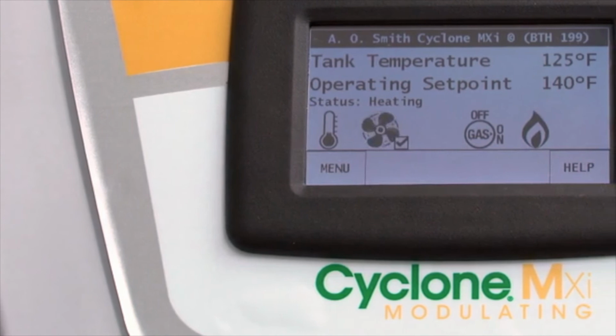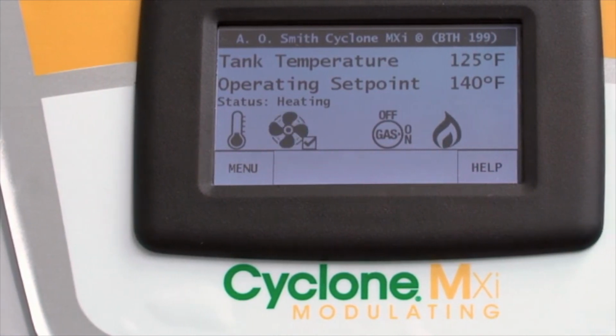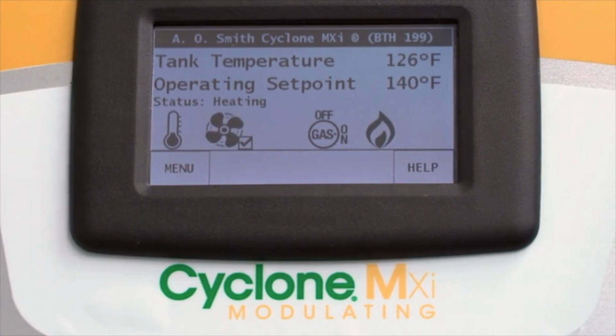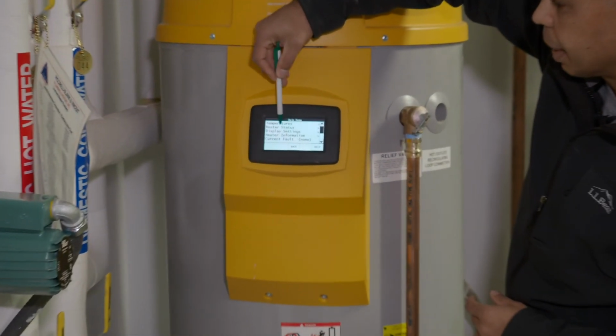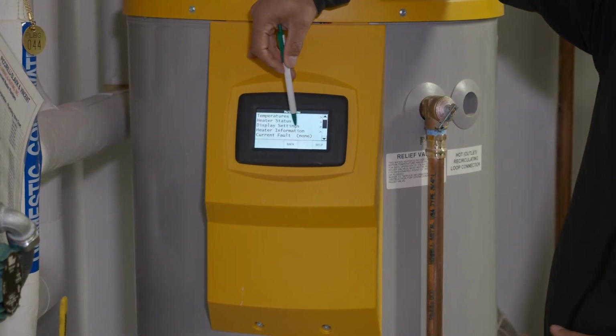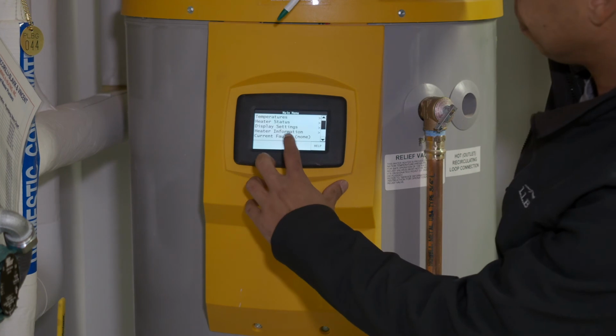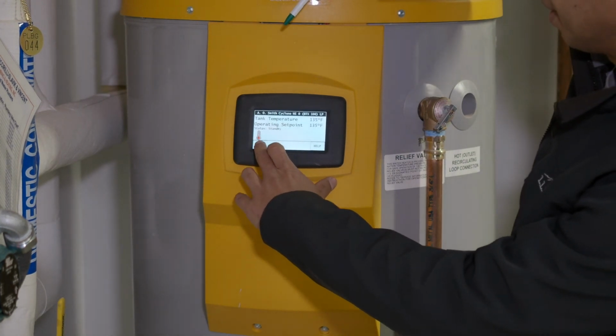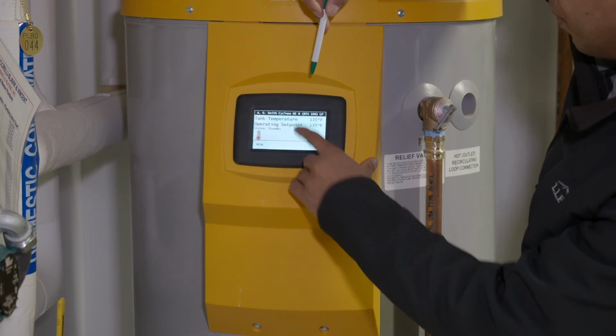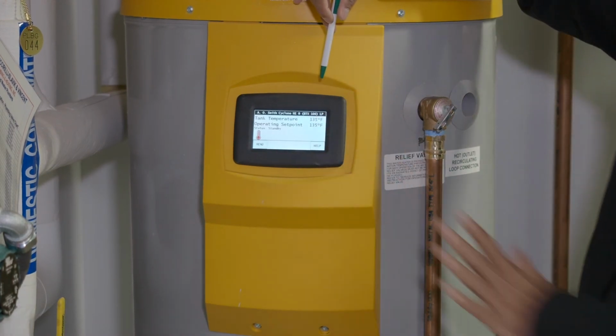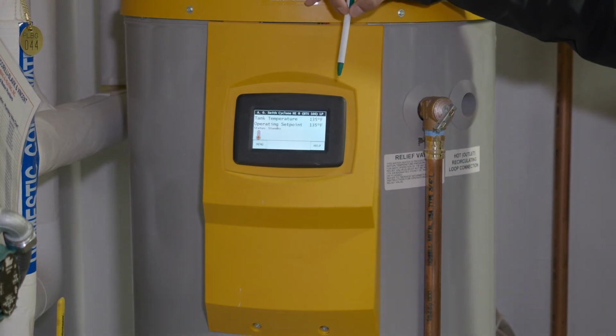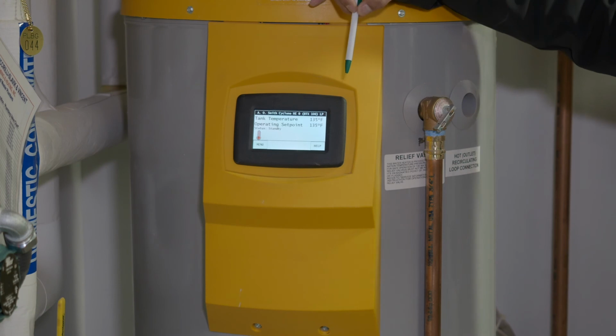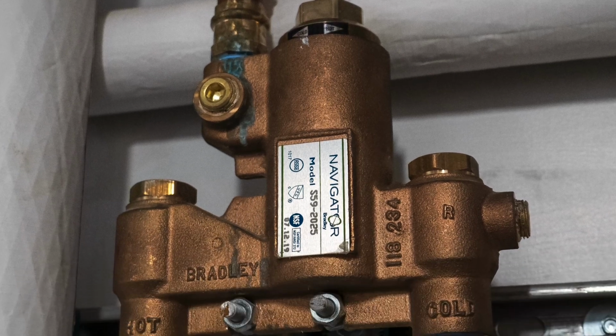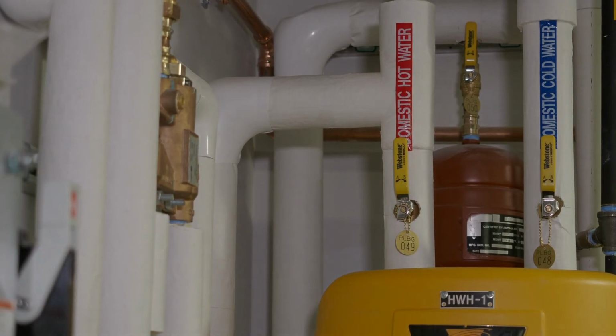The Cyclone MXI touchscreen display is just one more innovation that makes Cyclone the most advanced commercial gas water heater you can buy. Temperature, heater status, display, heater information, and current faults if there is one. If you have to, you go through the settings here. You could actually set what temperature you want. Typically, for this type of water heater, you set it at about 120 to 140 degrees. You do have a thermostatic mixing valve here, so you drop the temperature down so you don't get scalded at the end of your fixtures. And that's really the basics of this water heater.